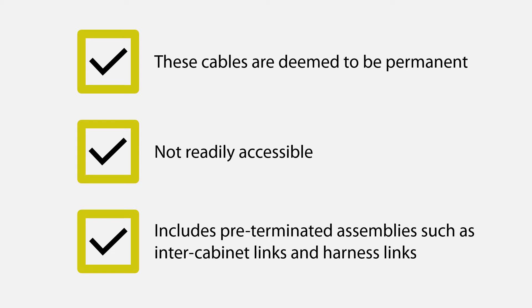If they are routed within the cabinets and along pathways in such a way so they are not easily removed, then they are in scope of the CPR and need to be made from compliant cable.